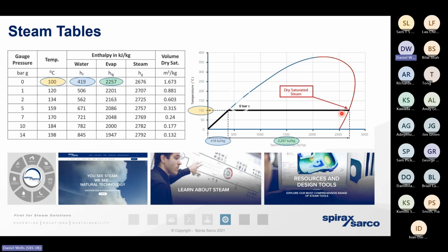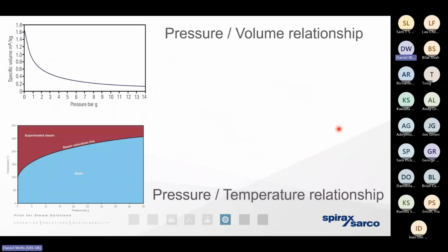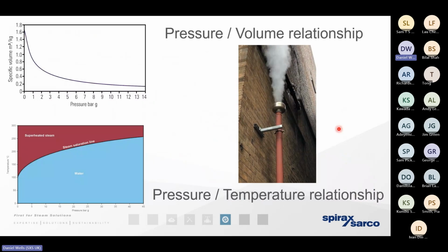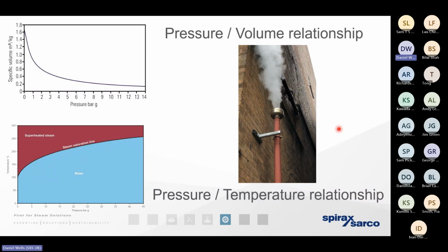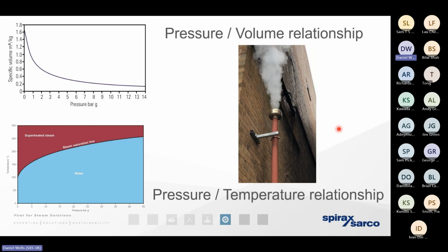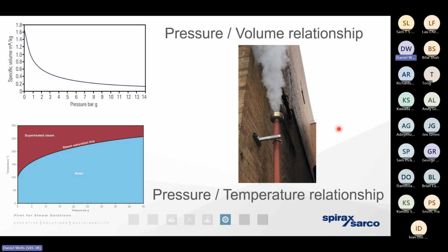The two benefits, well, it means the heat exchanger is likely to be sized correctly, and it also means that the boiler doesn't have to work harder to replace the steam that is condensing in the pipework. So the idea really is for us to get the steam to the point of use as close to that red dry saturated steam line as we possibly can. So last week we spoke about those two fundamental relationships in some detail, the pressure volume and the pressure temperature relationship. And we also understand that one of the fundamental causes of an inefficiency in a steam system is when a steam trap fails in the open position.